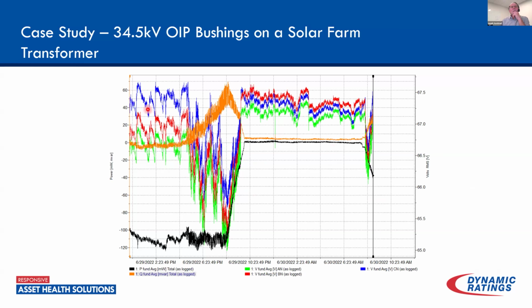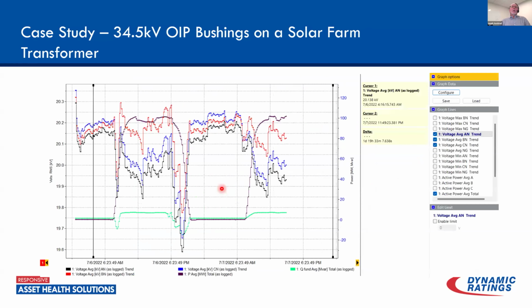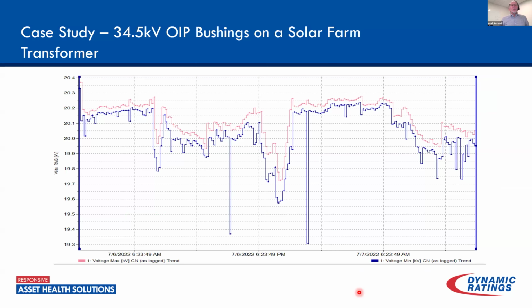This is that load profile we talked about before, the voltage fluctuations, all of which is driving some of that imbalance we're seeing on the system. But especially on the low side, it made it challenging to identify whether we have any bushing problems going on. This is just looking at the voltage profile a little bit differently. We can see again it's pretty stable, but once we start generating I start seeing increases, and when we're ramping it back down or bringing it back online, I start seeing even greater increases. So all of these voltage deviations are maybe driving those spikes in the imbalance current, making the data hard to understand and to identify whether we have a bushing problem. There are also short-term things, as the inverters react to problems on the system.